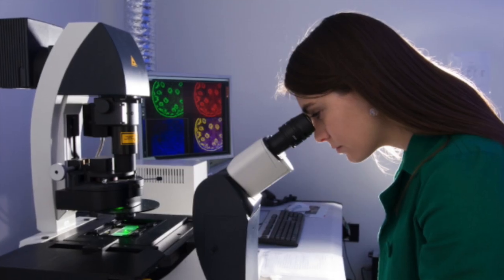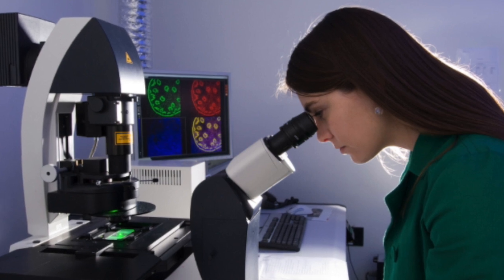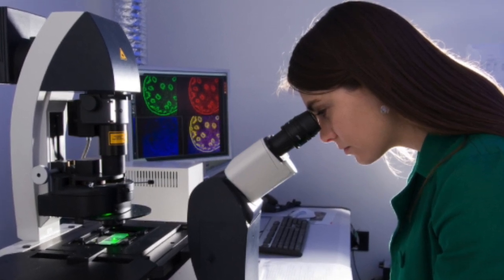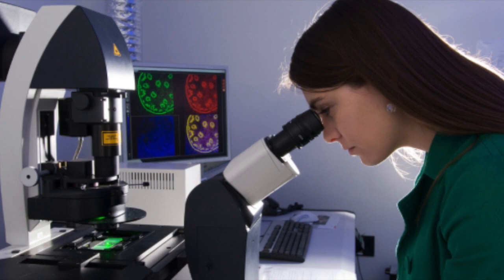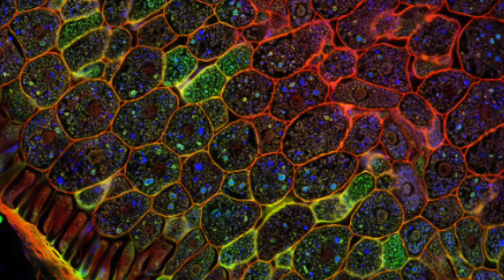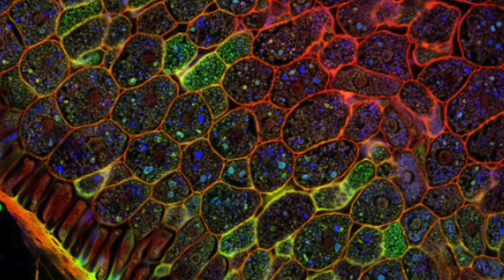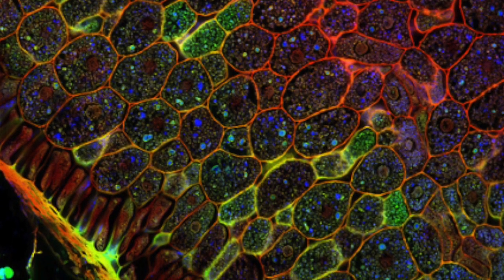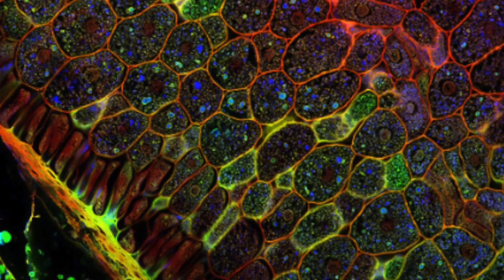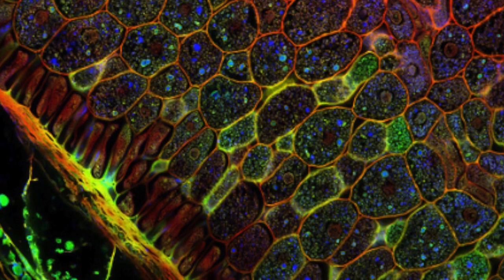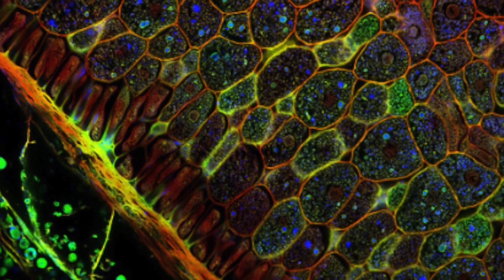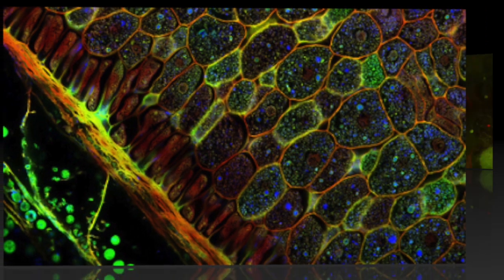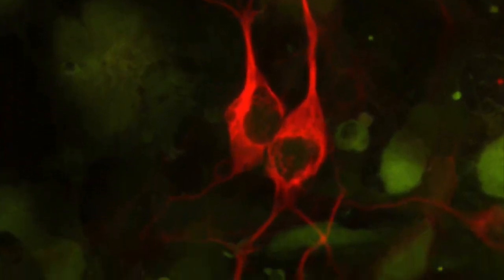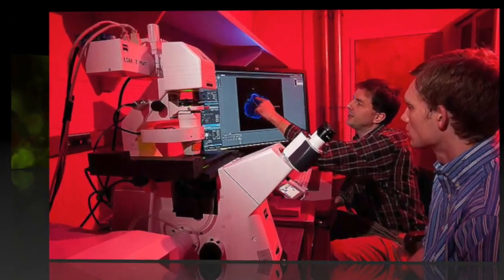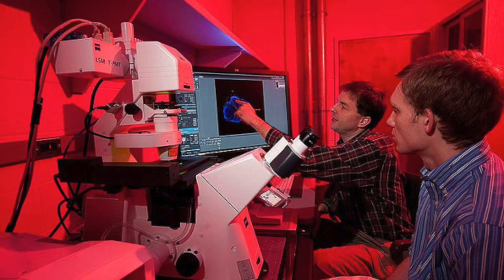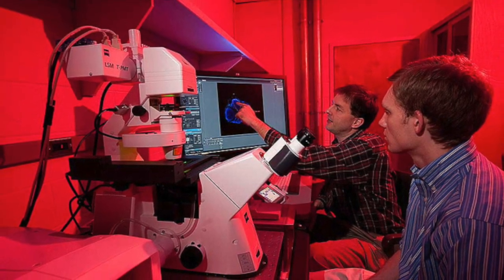Some laser light is passed back through the objective lens and the dichromatic mirror up to a second pinhole found near the photomultiplier detector at the top of the microscope. On the board are pictures of plant tissue and stem cells being viewed under a confocal microscope. The reason these specimens are being viewed through a confocal microscope rather than a compound microscope is because of the depth of the specimen. Confocal microscopes allow us to view specimens as thick as 100 micrometers and at a higher resolution than we would be able to with a compound microscope.